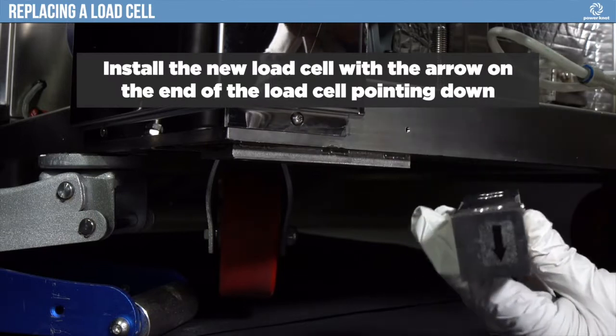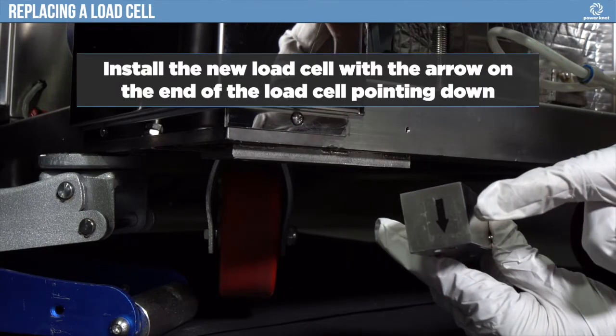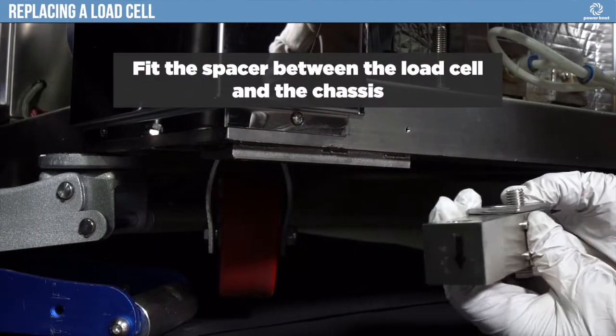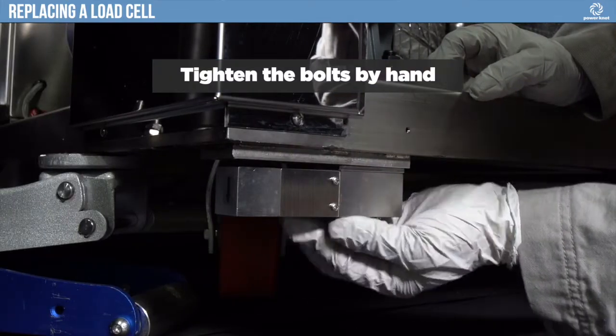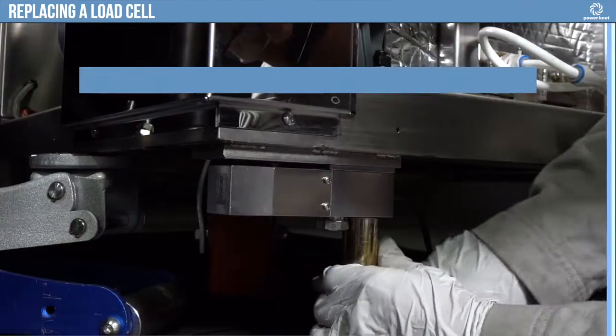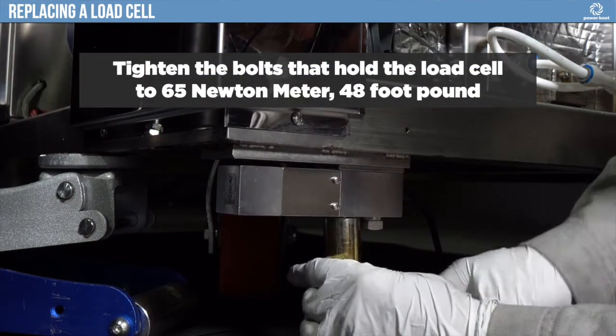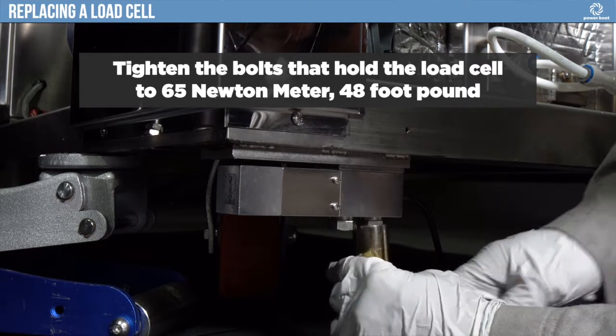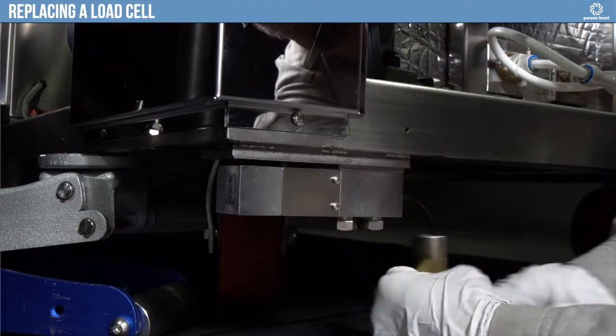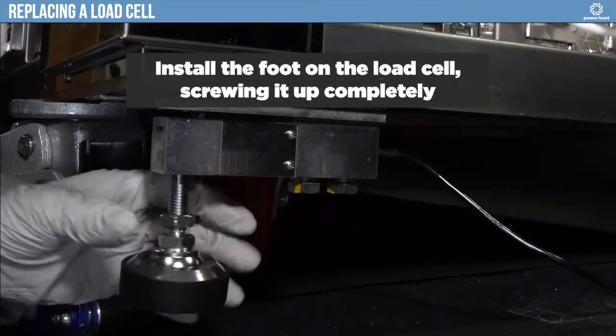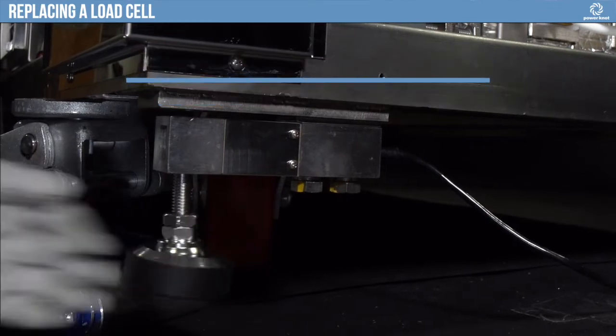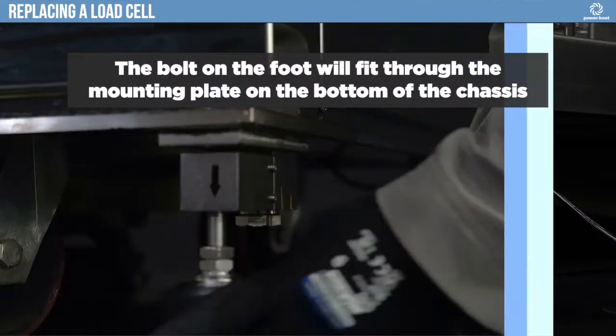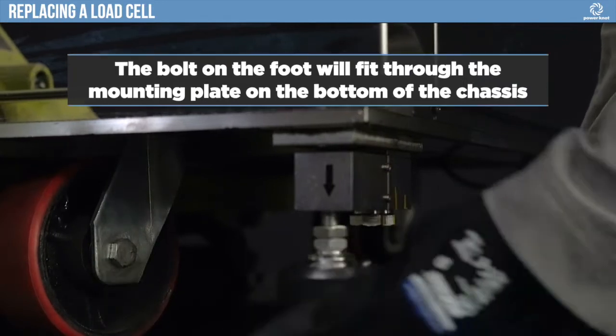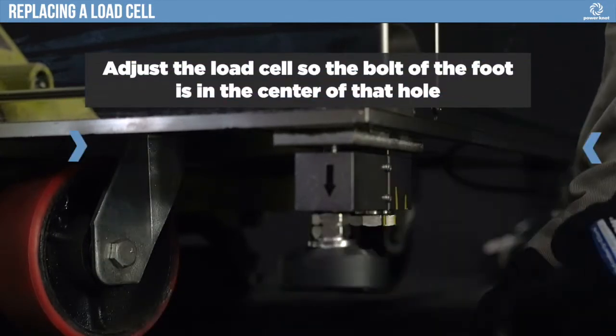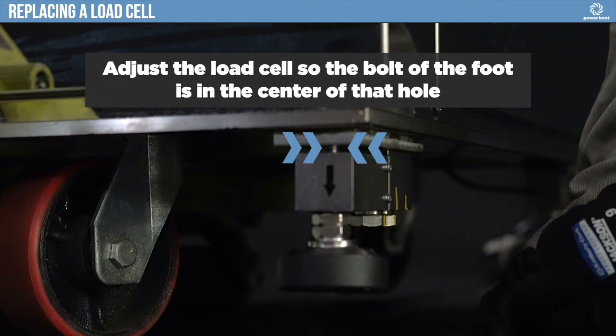Install the new load cell with the arrow on the end of the load cell pointing down. Fit the spacer between the load cell and the chassis. Tighten the bolts by hand. Tighten the bolts that hold the load cell to 65 Nm, 48 foot-pounds. Install the foot on the load cell, screwing it up completely. The bolt on the foot will fit through the mounting plate on the bottom of the chassis. Adjust the load cell so the bolt of the foot is in the center of that hole.